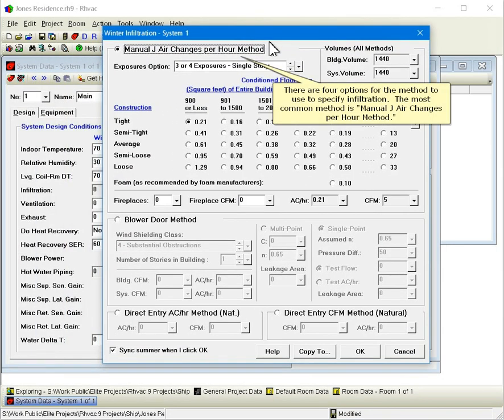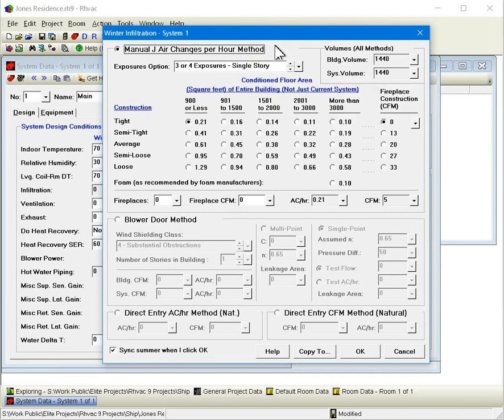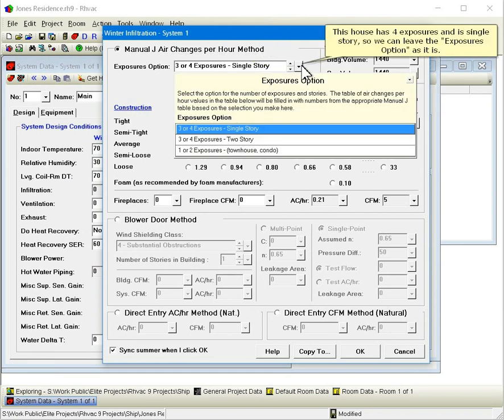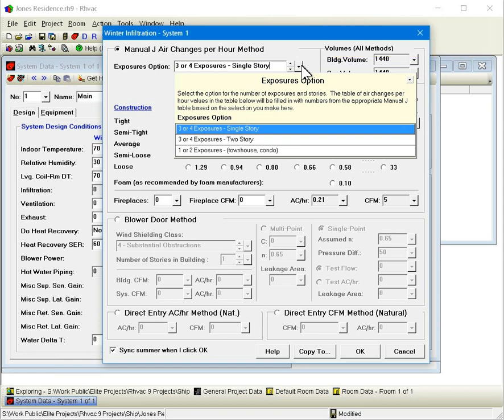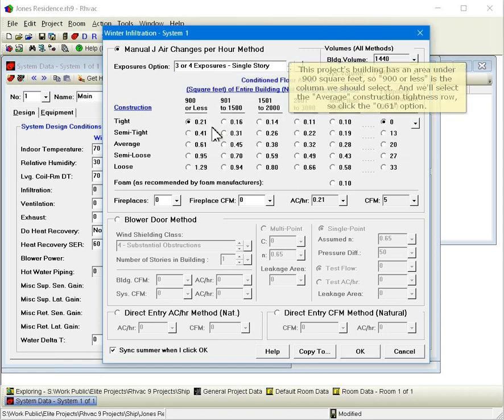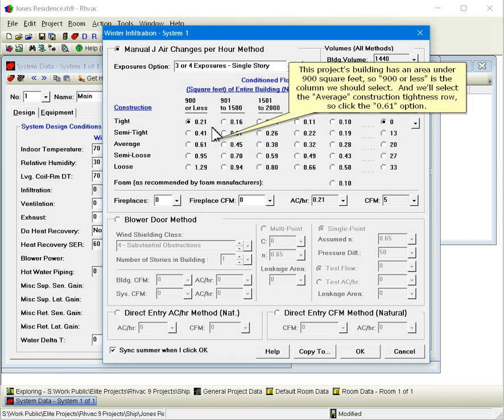There are four options for the method to use to specify infiltration. The most common method is manual J air changes per hour method. This house has four exposures and is single story, so we can leave the exposures option as it is. This project's building has an area under 900 square feet, so 900 or less is the column we should select.